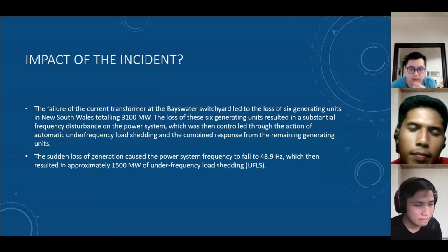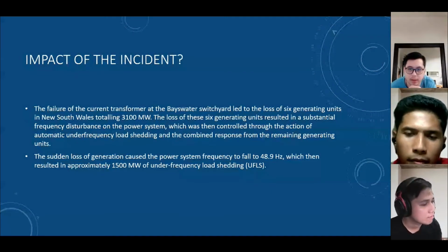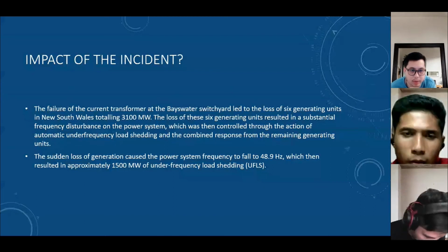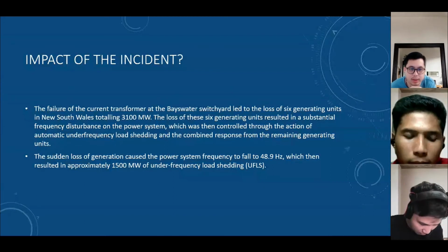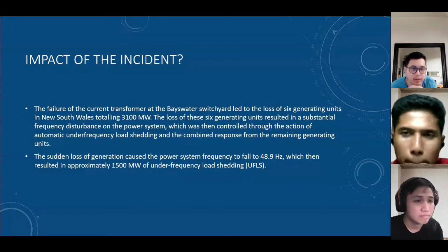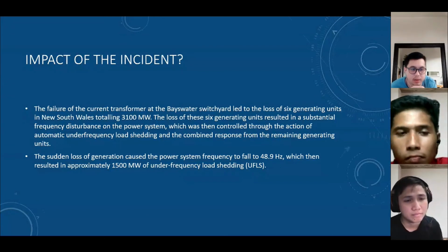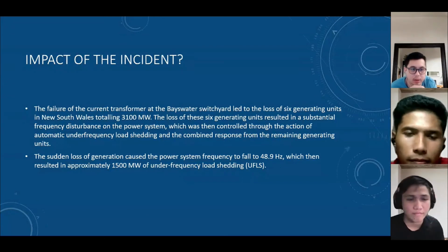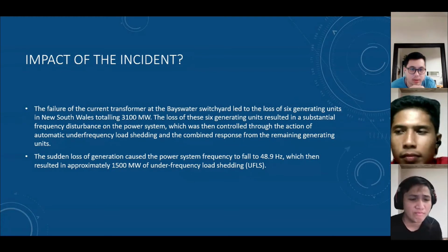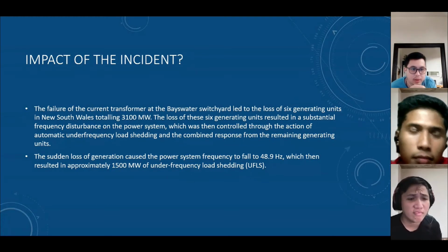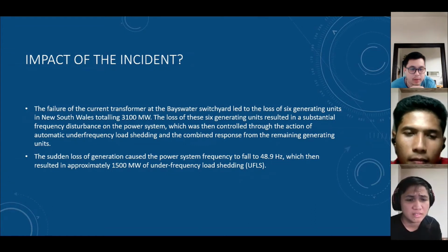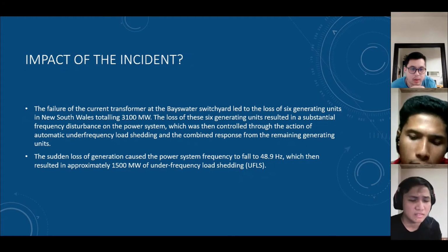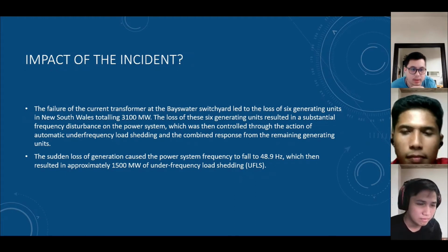So the impact of the incident: the failure of the current transformer at the Bayswater switchyard led to 6 generating units being lost in New South Wales, totaling around 3,100 megawatts. The loss of these 6 generating units caused a substantial frequency disturbance on the power system, and the sudden loss also caused the system frequency to fall to 48.9 hertz.